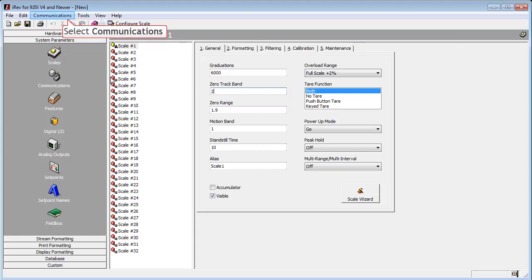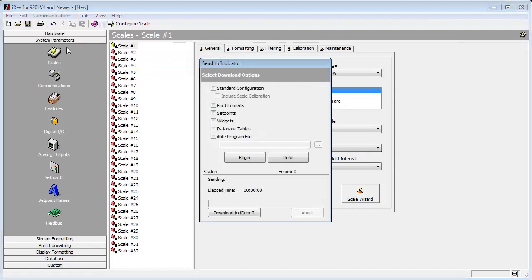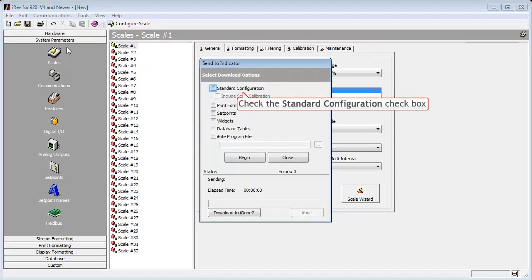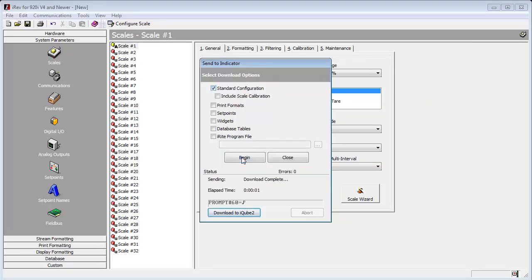Now to get this information into the indicator, we will go to Communications, and select Download Configuration. Since we only set up a scale in its parameters, we will select the Standard Configuration checkbox, and then hit Begin.